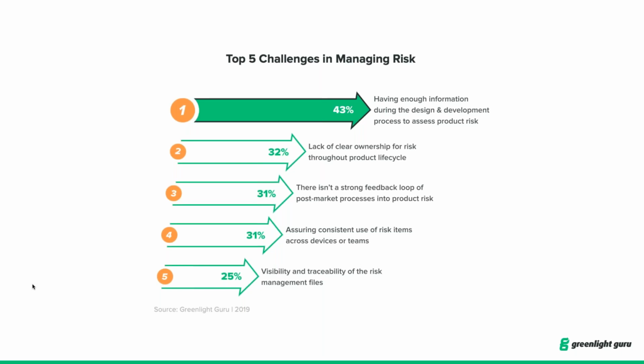And in my own experience, at least early on in my career, we started to do a lot of FMEA type approaches, failure modes and effects analysis. But the challenge with that tool is your product has to be pretty well vetted. You generally have a pretty good idea of the parts, pieces, components, et cetera that are going to go into your medical device.